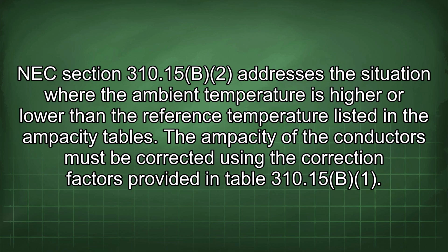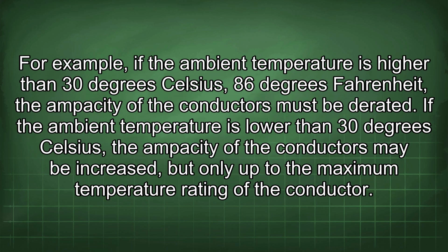NEC section 310.15(B)(2) addresses the situation where the ambient temperature is higher or lower than the reference temperature listed in the ampacity tables. The ampacity of the conductors must be corrected using the correction factors provided in Table 310.15(B)(1). For example, if the ambient temperature is higher than 30 degrees Celsius, 86 degrees Fahrenheit, the ampacity of the conductors must be derated. If the ambient temperature is lower than 30 degrees Celsius, the ampacity of the conductors may be increased, but only up to the maximum temperature rating of the conductor.